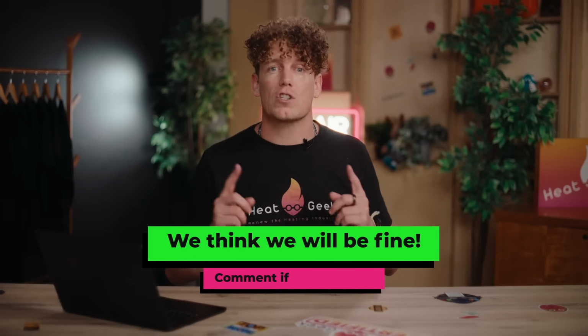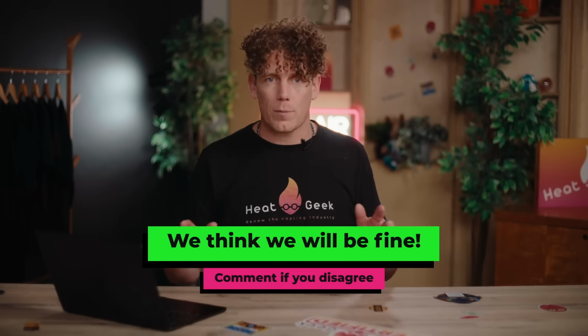So a few of you might be wondering if running the heat pump in this way may break it. Although it's true that sustaining high temperatures from the heat pump can cause oil thinning and breakdown, this spends nowhere near enough time to risk that, and is also prevented by the compressor discharge temperature limits, as well as other parameters. Now, this will almost certainly work in much larger properties than you would think, as people don't really start their showers at the same time, and it should in theory stop the water while they soap up.